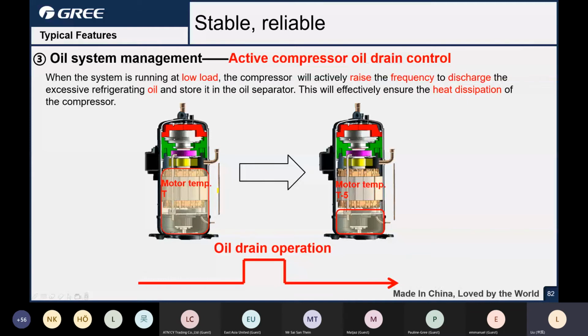So if there is too much oil in the chamber, it will cause poor heat dissipation. The heat dissipation of the compressor may be poor. So if too much oil inside, the GMV6 compressor can actively discharge the oil to the oil separator. Okay.